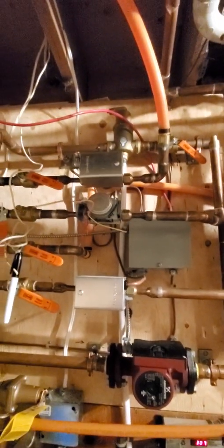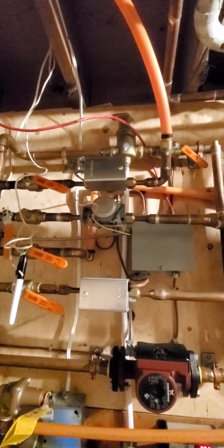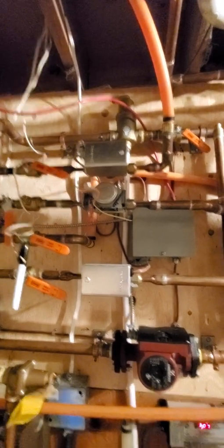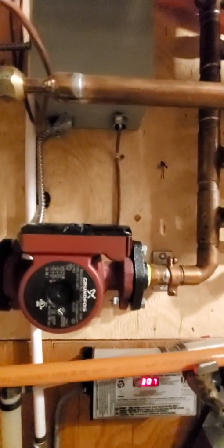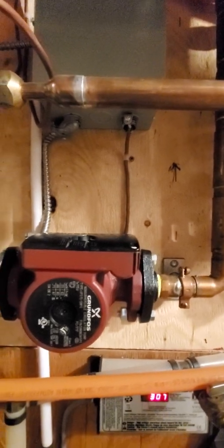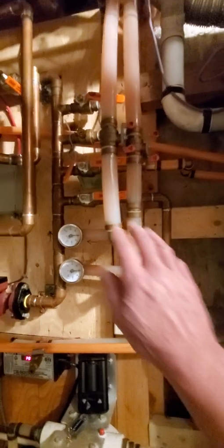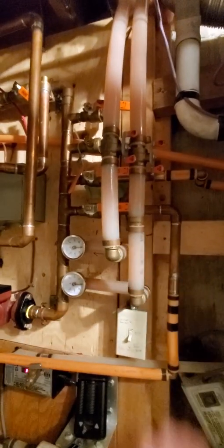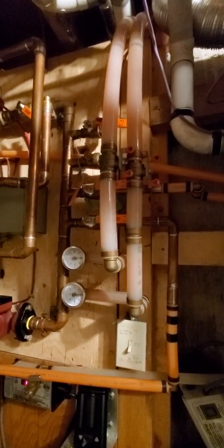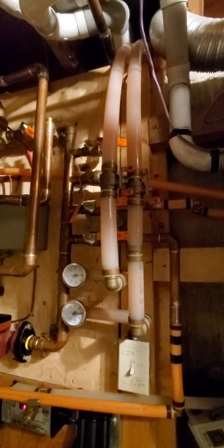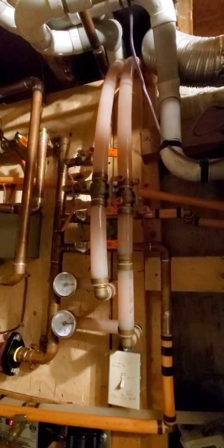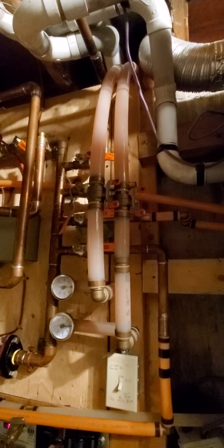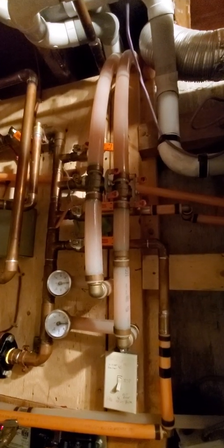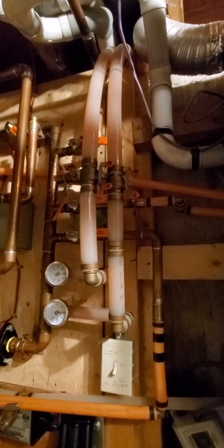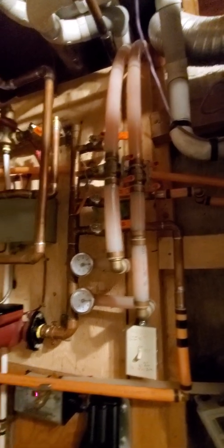Each one of these I've just got a zone valve on, so when it calls for heat, the zone valve opens and it just circulates. As well, we have another Grundfos pump here. These 2 lines I run back to my other boiler that's a gas boiler, and I can heat the gas boiler glycol before it goes into the unit. I can preheat it, so that thing just idles unless it gets to colder than -20, and then we kind of go off both systems.